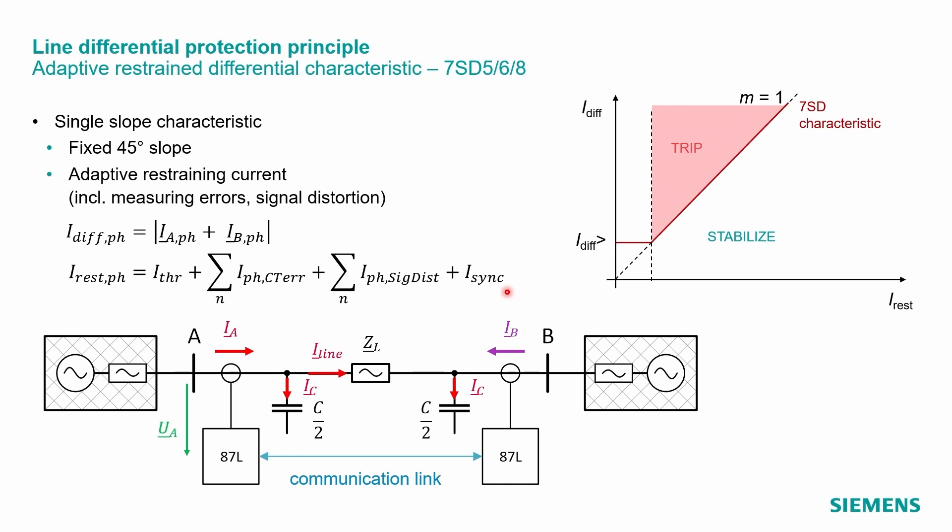Therefore, the stabilization characteristic looks different and is a single slope of 45 degrees, so M equals one. We provide a setting for the minimum differential pickup current. This should set higher than the expected capacitive charging currents. A differential current above the characteristic will trip the circuit breaker, or the relay will trip the circuit breaker. And below the characteristic the relay will stabilize.